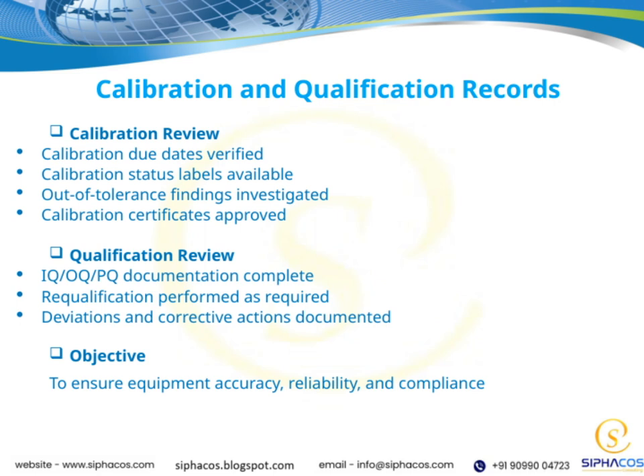If any out-of-tolerance findings are identified, they are promptly investigated to determine the cause and necessary corrective actions. Additionally, all calibration certificates are carefully reviewed and approved, confirming that the calibration process meets our quality standards. Moving on to qualification review, we ensure that all IQ, OQ, and PQ documentation is complete.